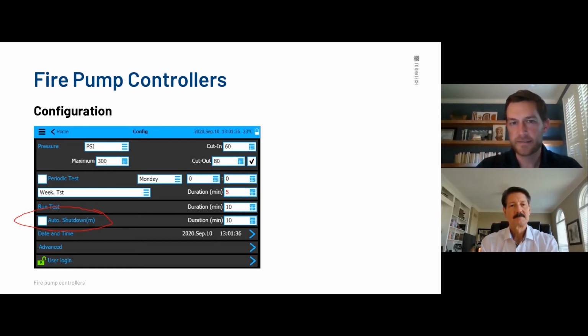So very, very easy to field program these control panels with those types of adjustments. You can change the date and time here as well, depending on how long your control panel has been sitting. You know, sometimes at the job sites, our panels get delivered and then they sit for several months. So your date's probably going to be wrong, but it's very easy to change your date and time. You don't need a password to do that.